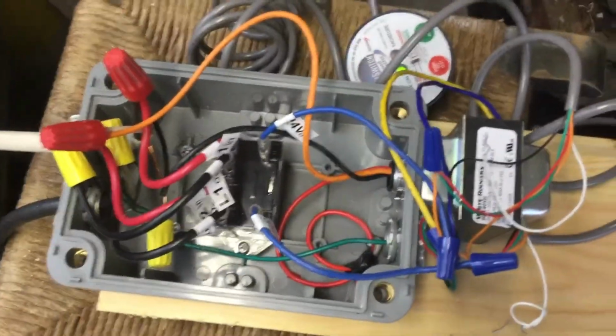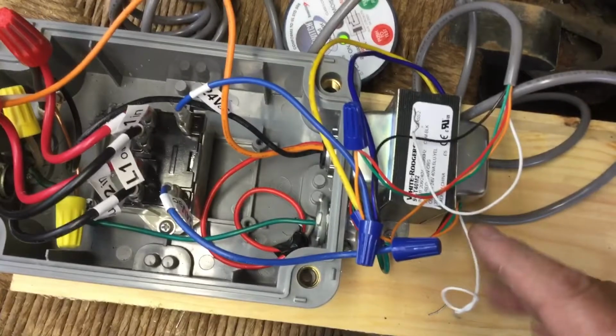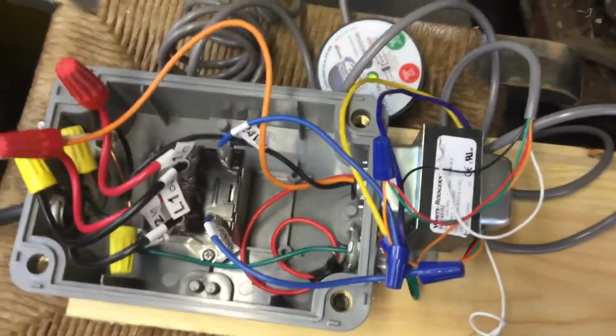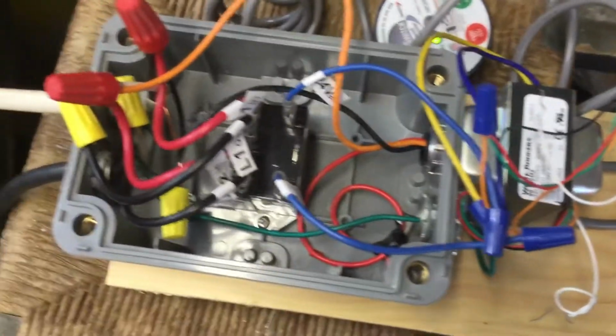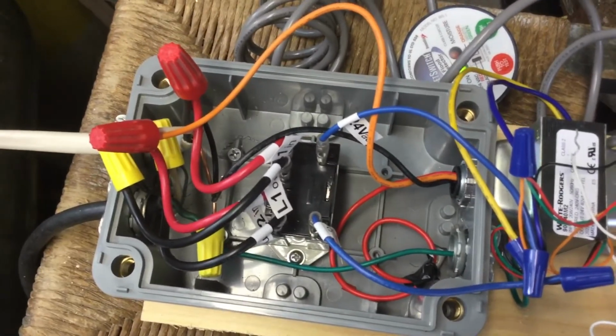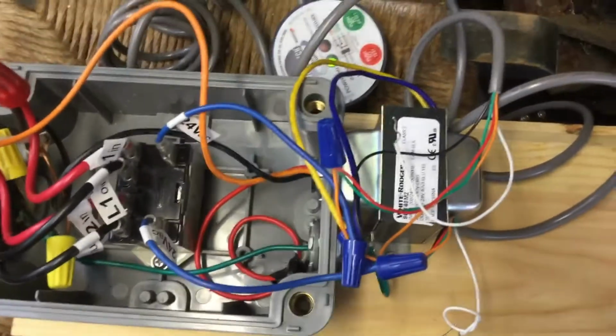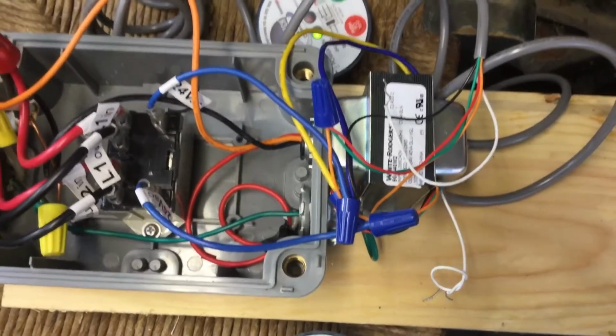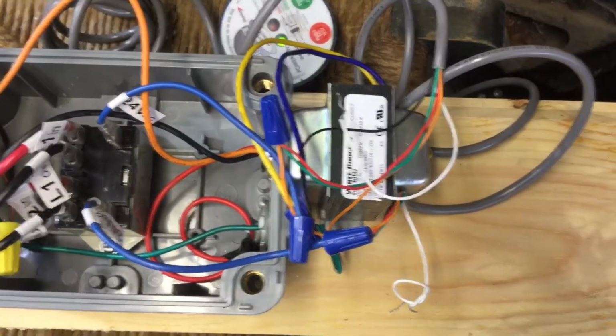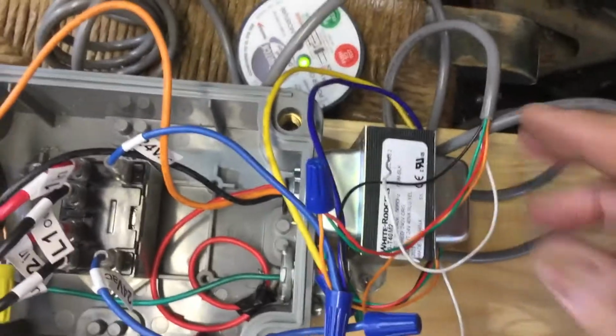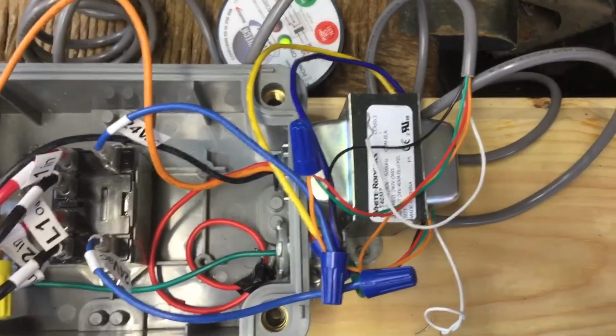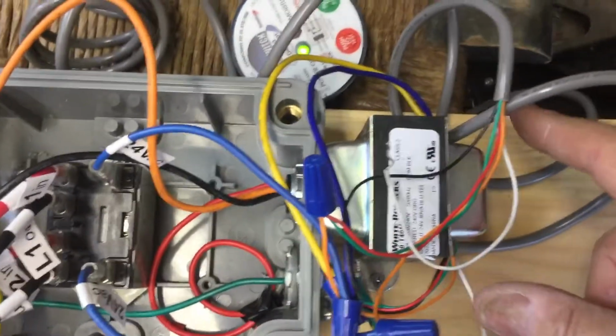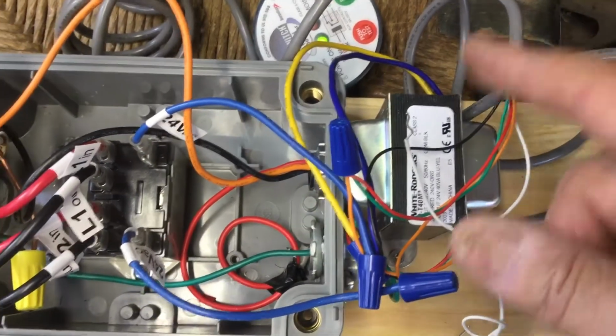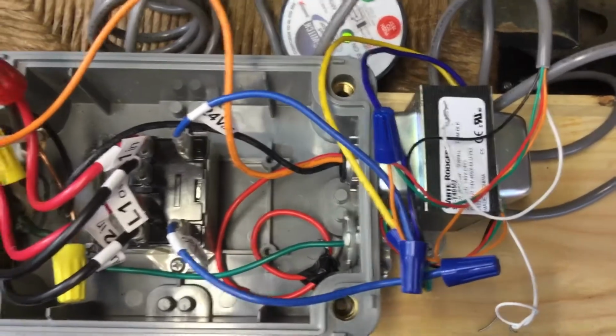On the other side, the transformer has two wires, the black and the orange. They tap into the house power coming in, and that powers the transformer. The transformer puts out, as I said, 24 volts. And that's the blue and the yellow line over here. So you hook that up. Those are the ones that get hooked up to the switches, and these two blue lines are for the relay.